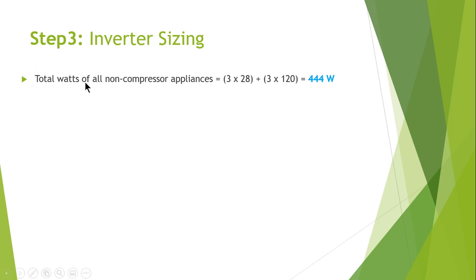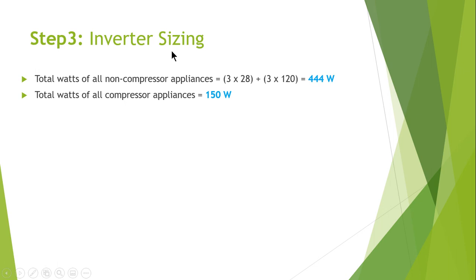In the next step, we estimate the inverter size. The total watts of all non-compressor appliances are: three bulbs (3 × 28) plus three fans (3 × 120), which equals 444 watts total for non-compressor motor appliances.